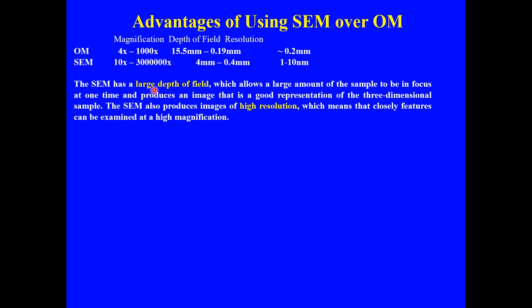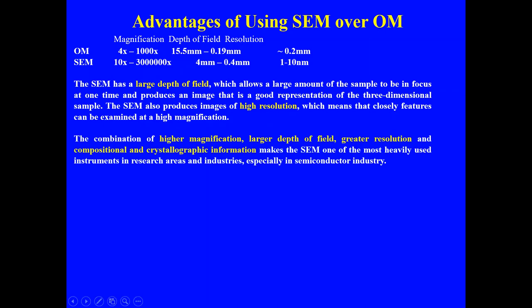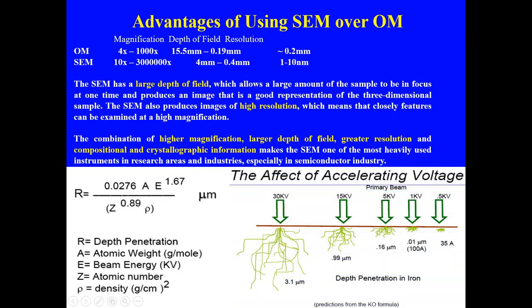The SEM has a large depth of field, which allows a large amount of the sample to be in focus at one time and produces an image that is a good representation of a three-dimensional sample. The SEM also produces images of higher resolution, meaning closely spaced features can be examined at high magnification. The combination of higher magnification, larger depth of field, greater resolution, and compositional and crystallographic information makes the SEM one of the most heavily used instruments in research and industry, especially in the semiconductor industry.